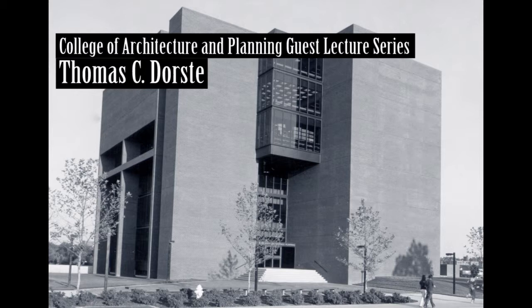So, you know, we'll find out in the future. This building led us into the next step. We were disenchanted with active solar heat, but we became interested in passive solar heat. It has a distinct and direct application to residential units, but we feel it has a distinct application to other types of buildings as well. A heat pump is a real neat piece of hardware to pick up excess heat. If you introduce monitors on a roof and orient the building properly so that you pick up the winter sun and heat the plenum air from the sun and pick that heat up in the heat pump units and store it in a water tank, you can reverse the whole process. You'd use it in the daytime in the perimeter and use it at nighttime to pick up the nighttime loss of the building.